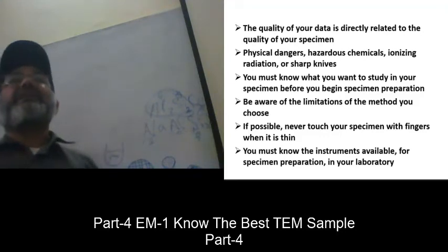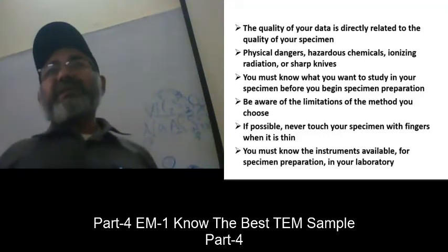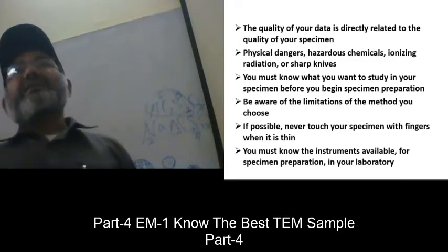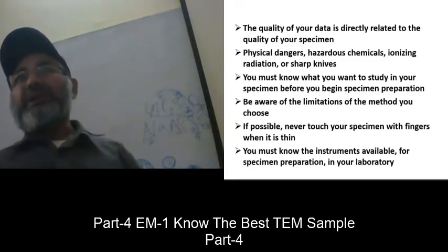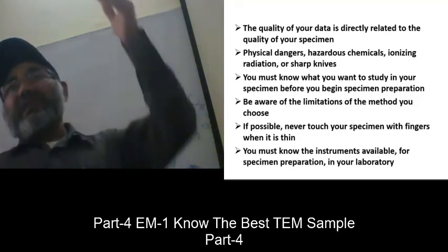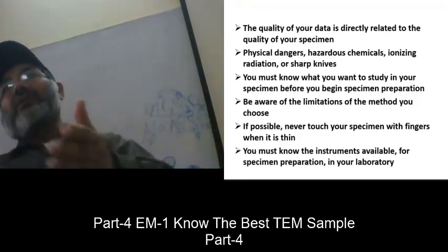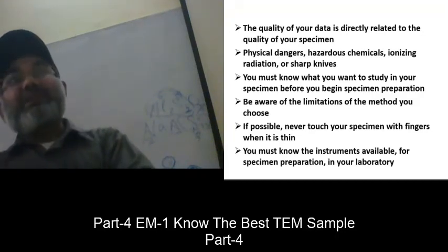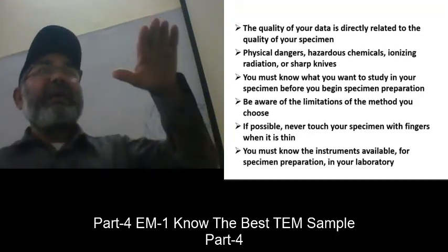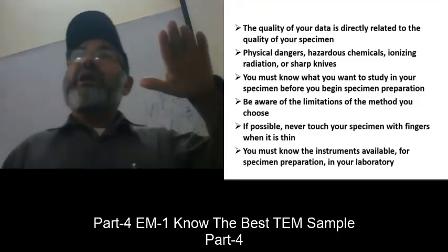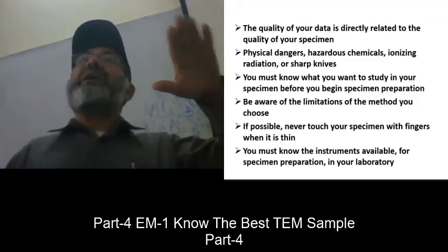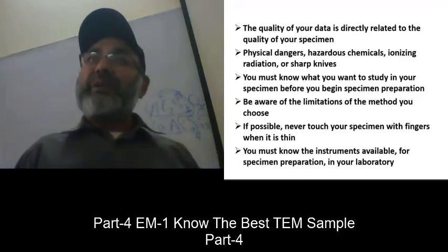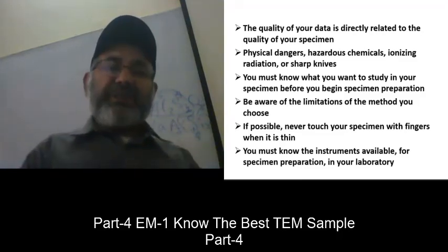But if your sample is an insulator, for example ceramic or quartz or glass, then you must carbon coat it so that electrons coming onto the sample find a way to neutralize. If they are not neutralized, then you will have a cloud-type thing over the sample and you will not be able to get a well focused and proper image of that material.